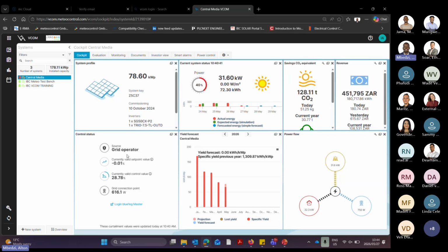And the current valid control value is 28.78%. So this is what's going to the inverters to say: inverter, produce 28.78% in order to not feed back. If the current valid set point were 100%, that means we're telling the inverters to produce at 100%. So that's the difference between current valid set point value and current valid control value.